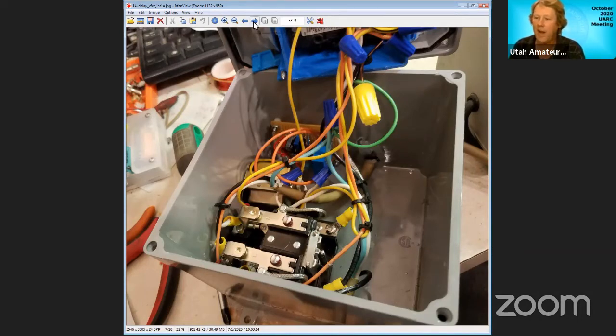So if the power goes away on the UPS, it disconnects immediately and goes to the B side. But if the power comes back, the power is not good yet because the UPS is ramping up slowly, as modern UPSs do. It takes about 2 or 3 seconds before the voltage stabilizes, before this thing makes the satisfying clunk.